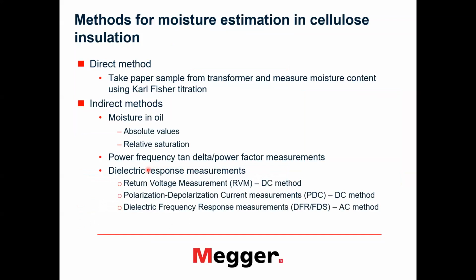So, continuing, what methods do we have for estimating moisture in cellulose? The most widespread and best method is, of course, a direct method. You use Karl-Fischer titration or similar to take a sample from the transformer and directly measure the moisture content. Then there are a number of indirect methods, like measuring moisture in oil in absolute values and relative saturation. We can do power frequency tangent delta power factor measurements, and of course we can do dielectric response measurements. Depending on what instrument is available, we can use DC methods and or AC methods.